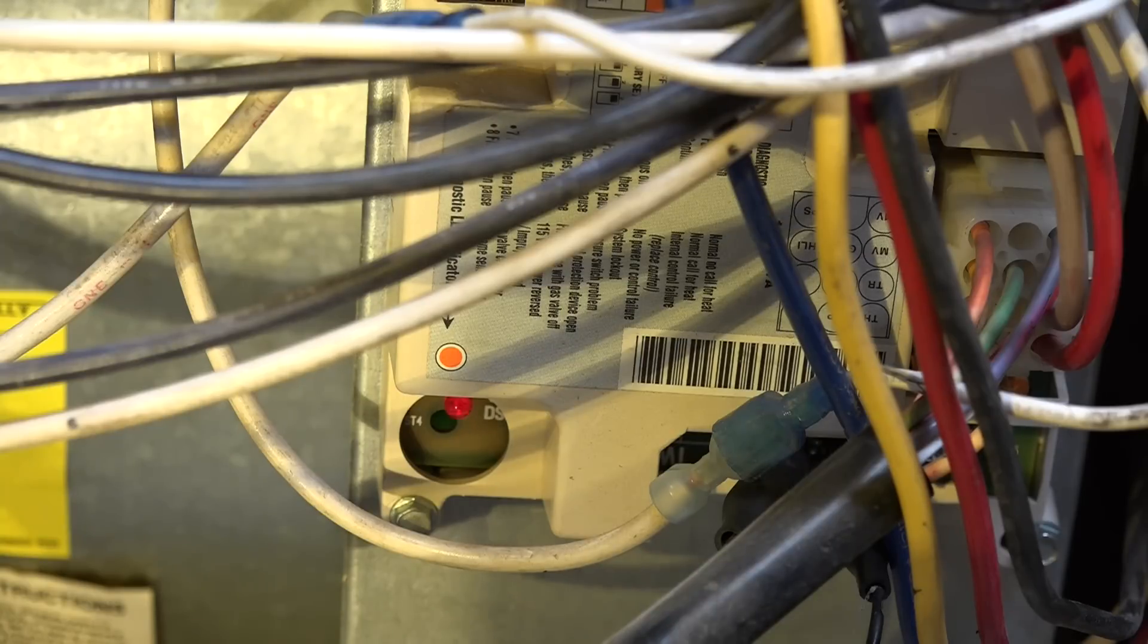Now if the pressure switch is stuck closed like the first video then it wouldn't turn on the inducer at all. But if the pressure switch didn't close the inducer stays on and it starts blinking a code.